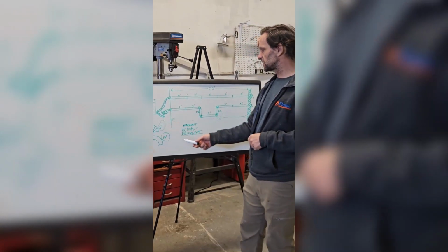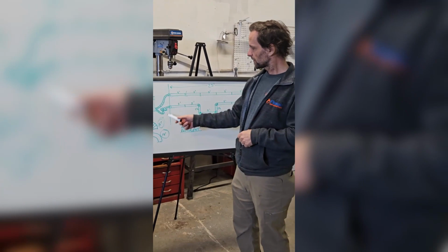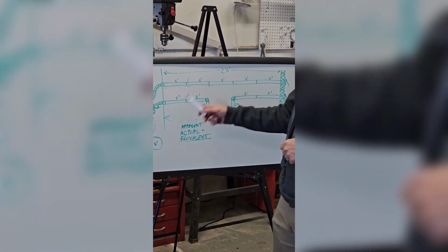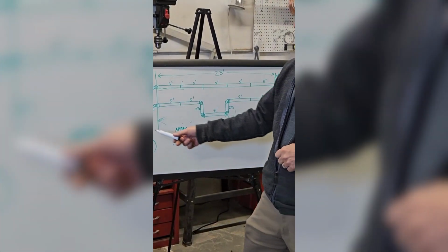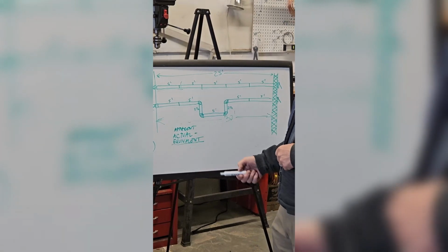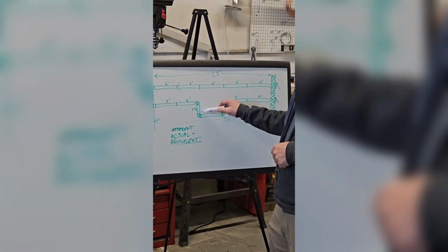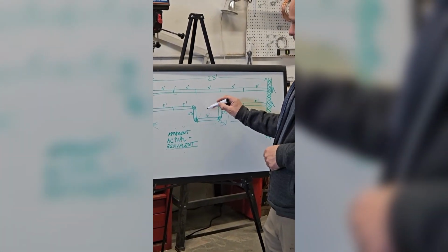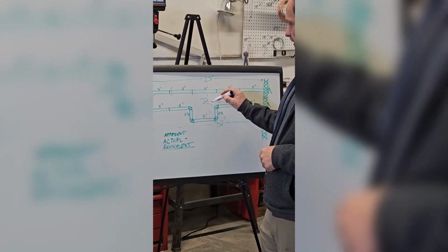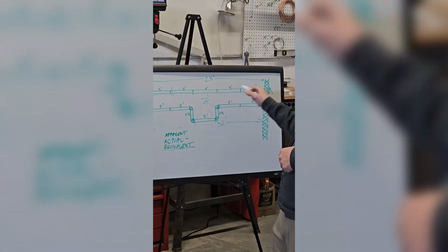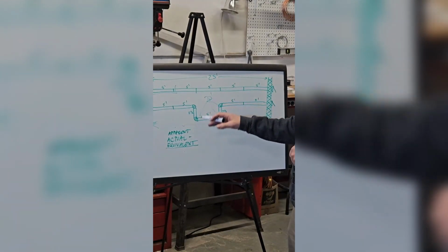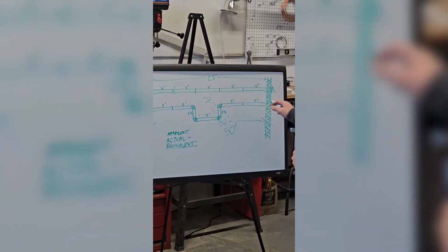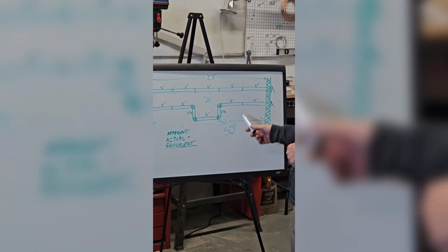Okay, so let's see what that means in this particular case. We said that this run has an actual length of 30 feet. But we have a sectional elbow that creates as much friction as 5 feet of straight duct, and we have 4 of these elbows. So 4 times 5 is 20. Just the elbows create the same friction as 20 feet of a straight run. So you have 30 feet of actual length plus 20. This run has an equivalent length of 50 feet.